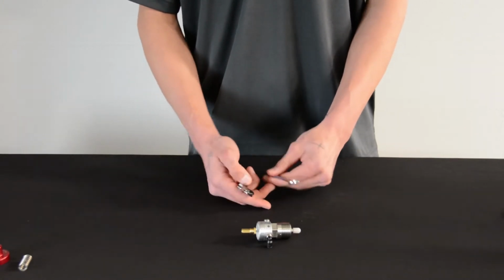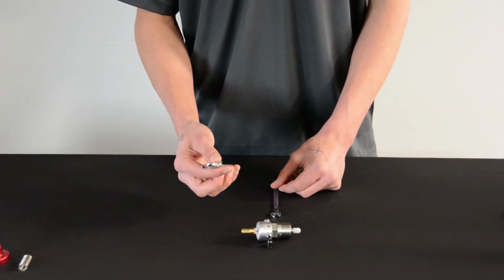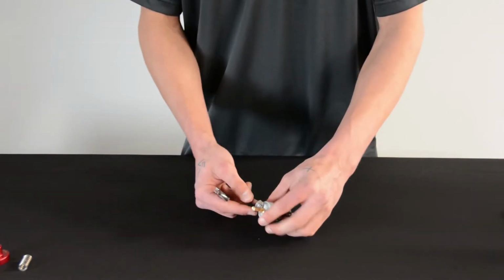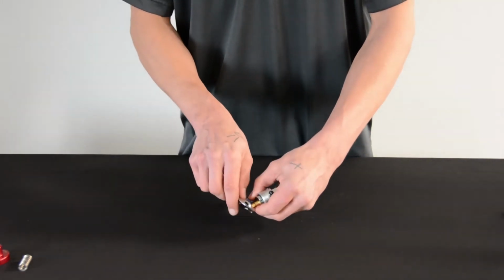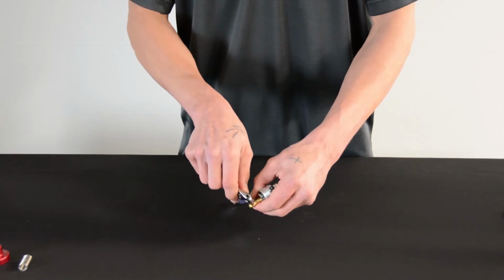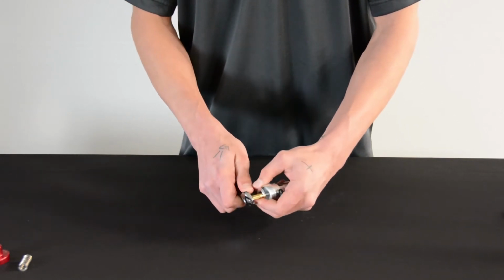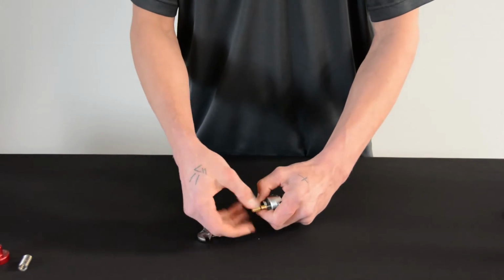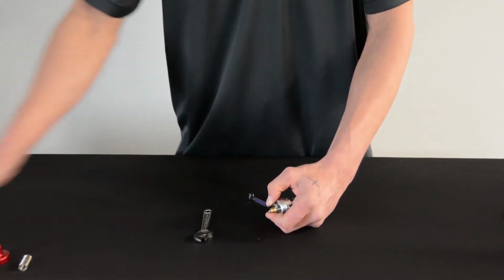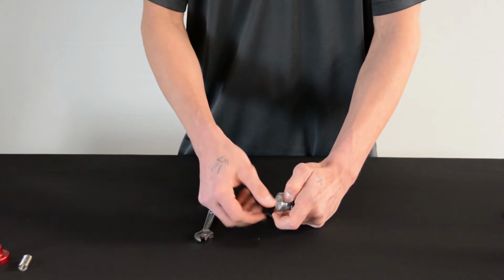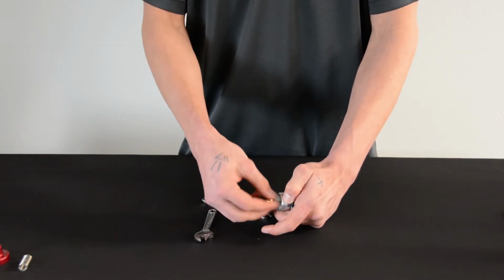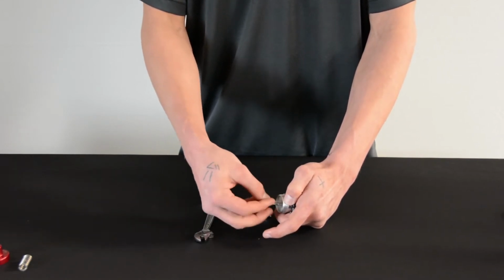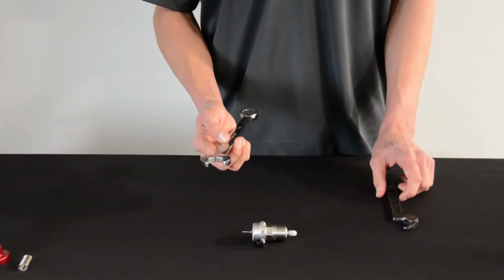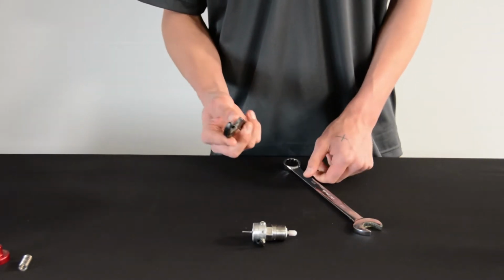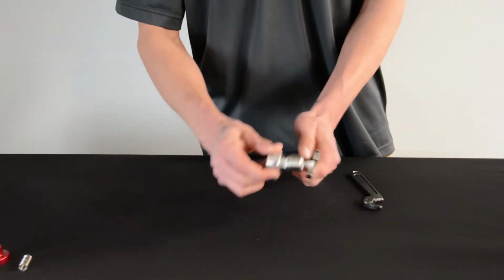Then take a 5/16 wrench and a 1/4 inch wrench, or a small adjustable wrench if you have one, and loosen the locking nut indicator from the piston retaining nut. You can put that off to the side, as well as your piston retaining nut. Then take your 7/8 wrench and your adjustable pin spanner wrench and remove the valve body from the piston body.